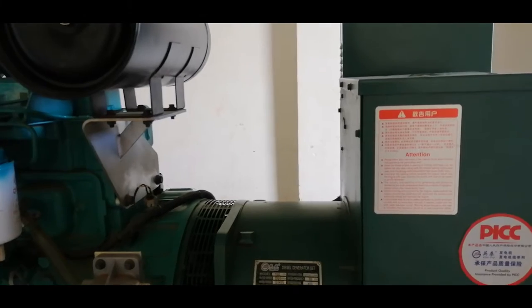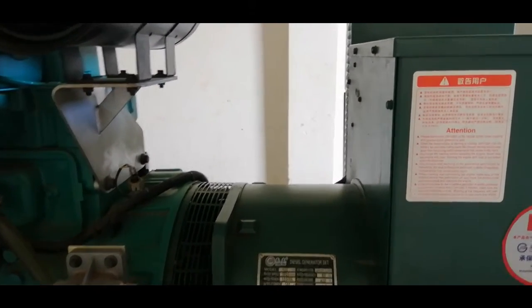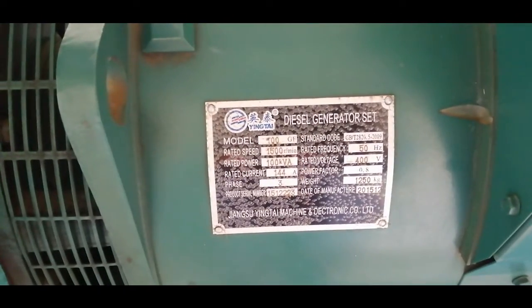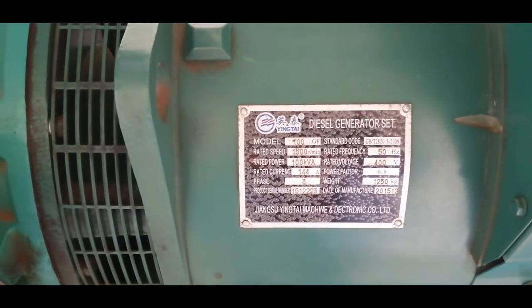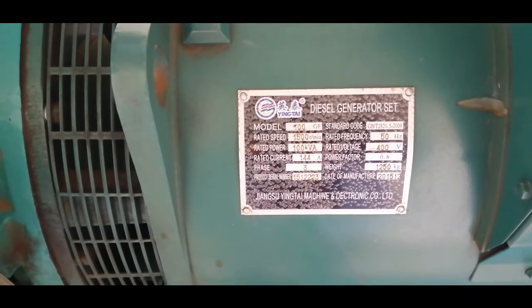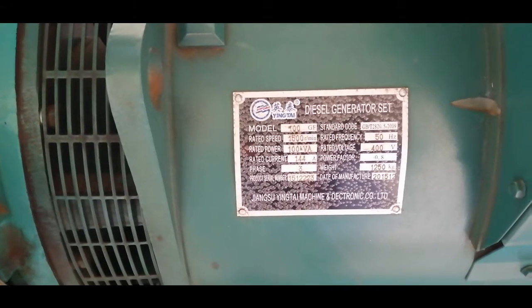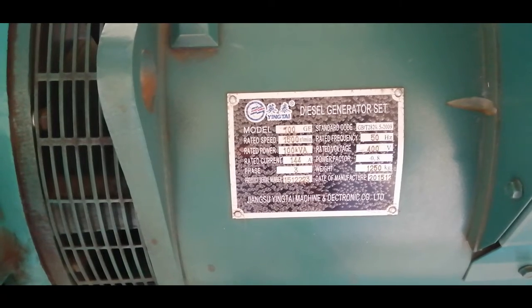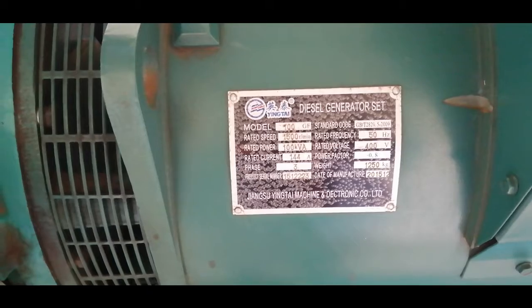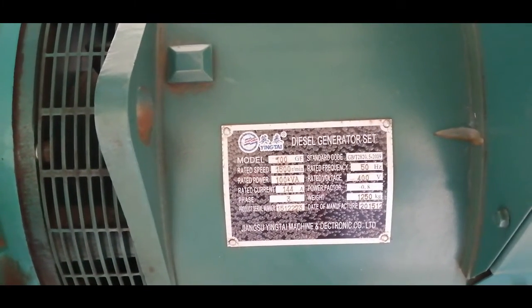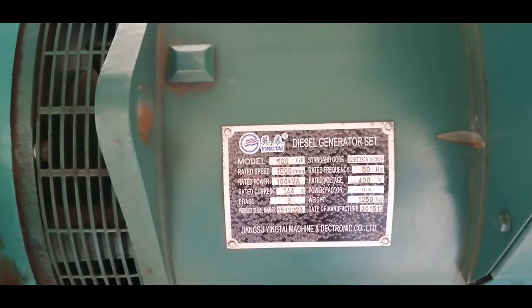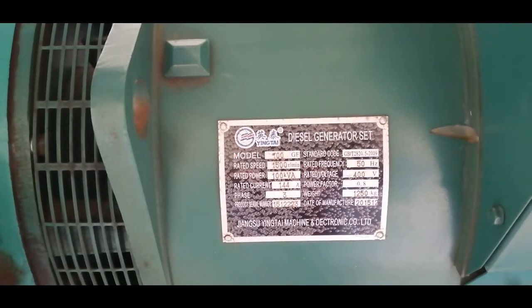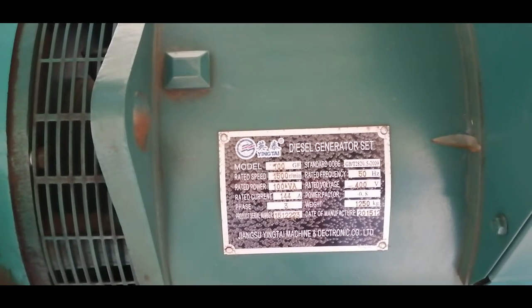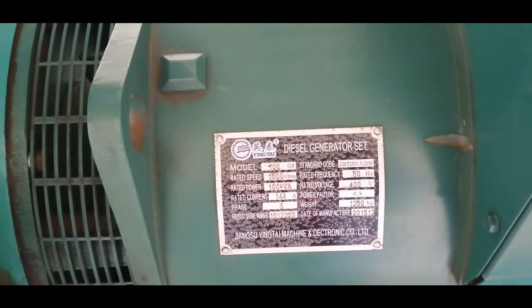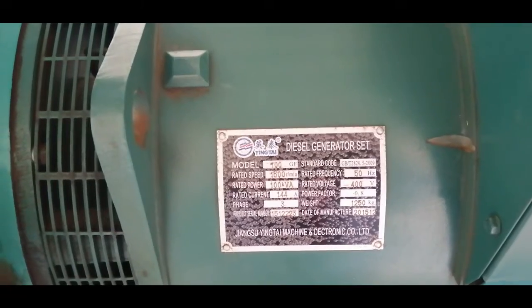Let's start by checking the nameplate of the generator. From the nameplate we can see the model and speed of the generator, and the rated power, which is 100 kVA. We note the rated current, 144 amps, and it is 3-phase, with the product serial number visible here. We can also see the rated frequency, 50 hertz, and the rated voltage, the power factor, and the weight, which is 1250 kg, and the date of manufacture. That is the part we can see from the nameplate.